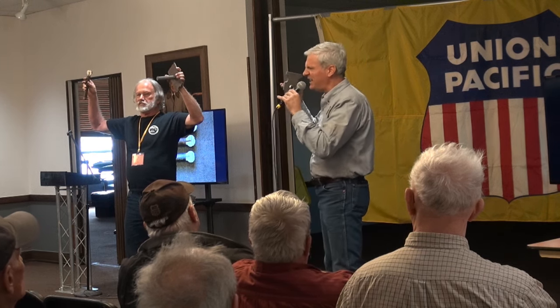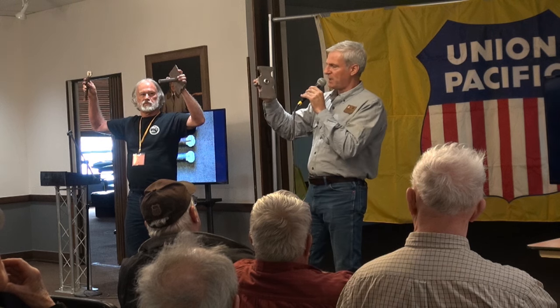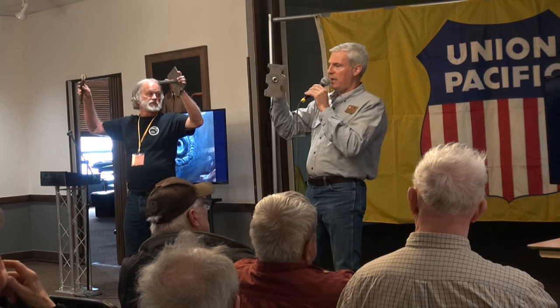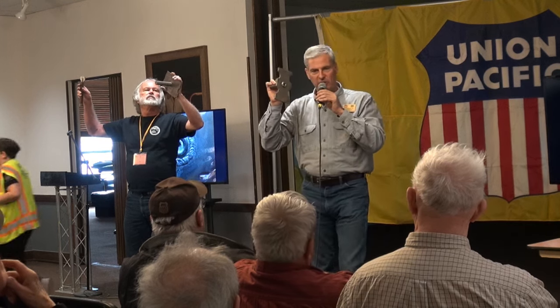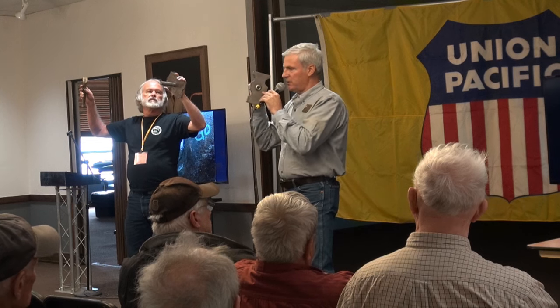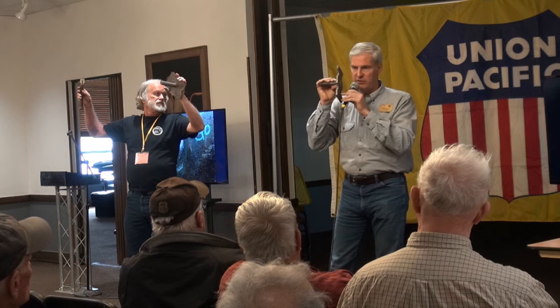You feel that. How many people shovel coal into a steam locomotive? When you open that fire door, what do you feel? You get a sunburn, and you wear sunglasses. That heat energy. Well, on this, that stay bolt has to survive that. I know it's difficult to see here, you can look at it in a few minutes. That structure has to be low profile, and there can be no little edges protruding out of there, because that fire is going to look for that, and that fire is going to destroy that metal. So you want the metal to be folded back into the heat transfer surface so the heat will dissipate through the metal. And you'd be amazed how quickly the heat runs through this and is transferred into the water.